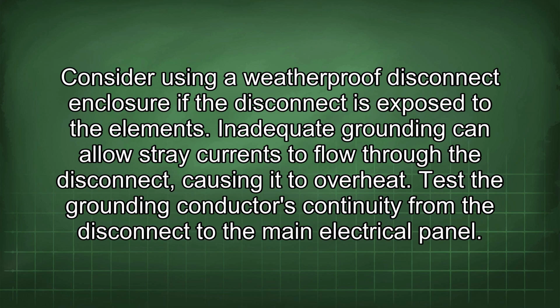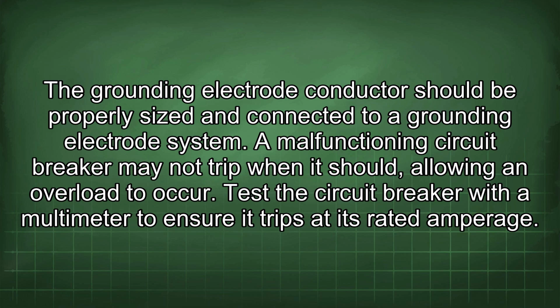Inadequate grounding can allow stray currents to flow through the disconnect, causing it to overheat. Test the grounding conductor's continuity from the disconnect to the main electrical panel. The grounding electrode conductor should be properly sized and connected to a grounding electrode system.